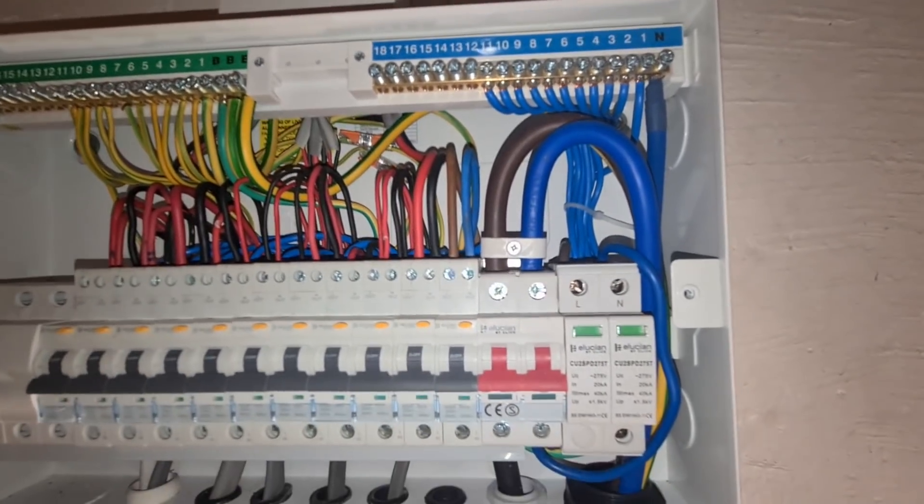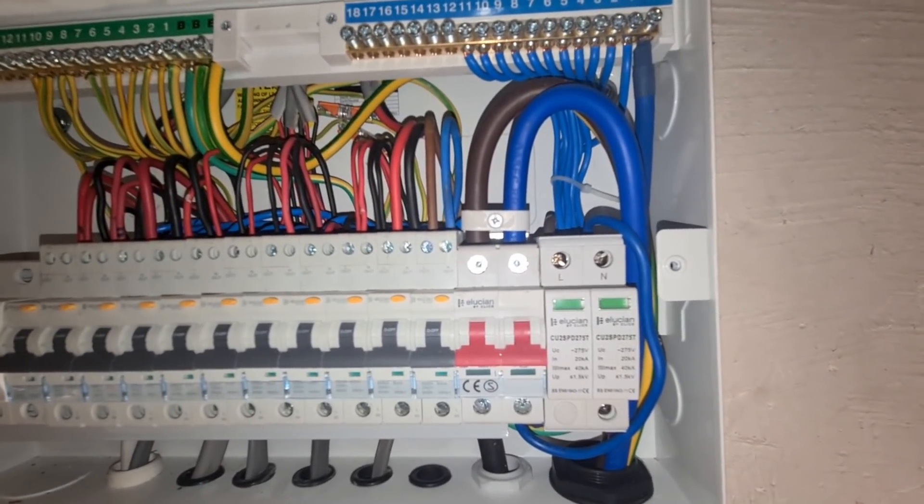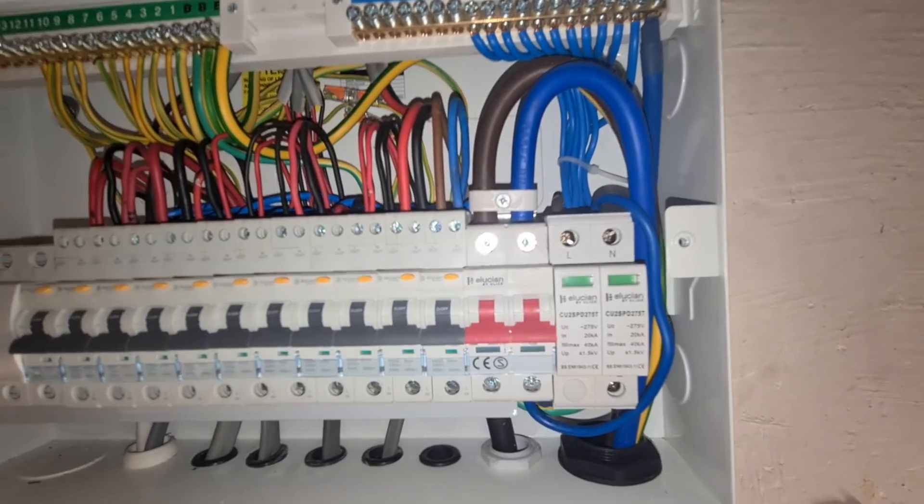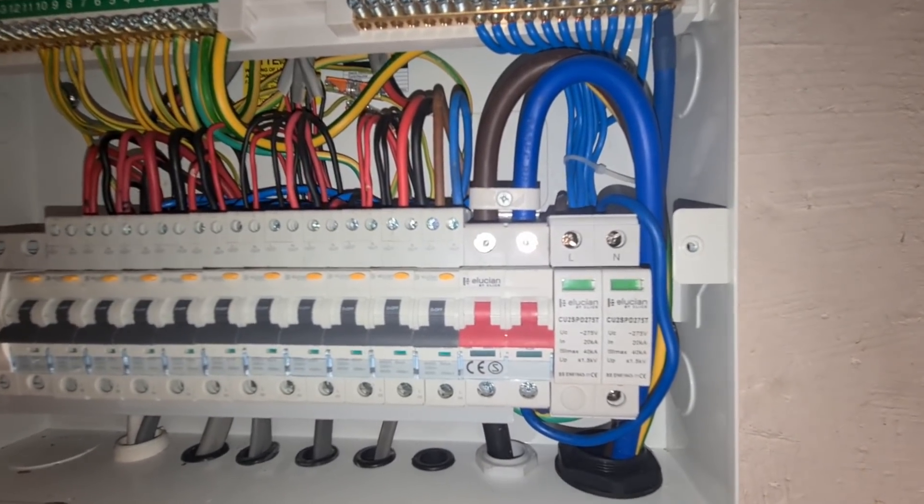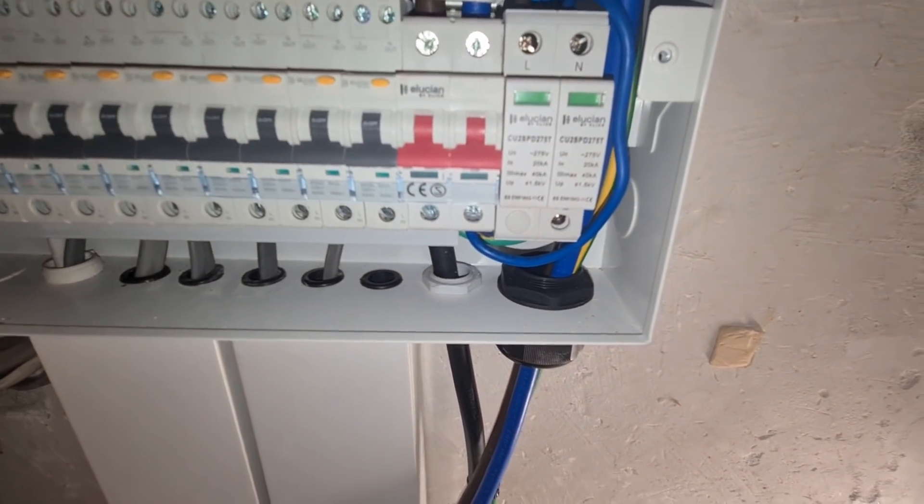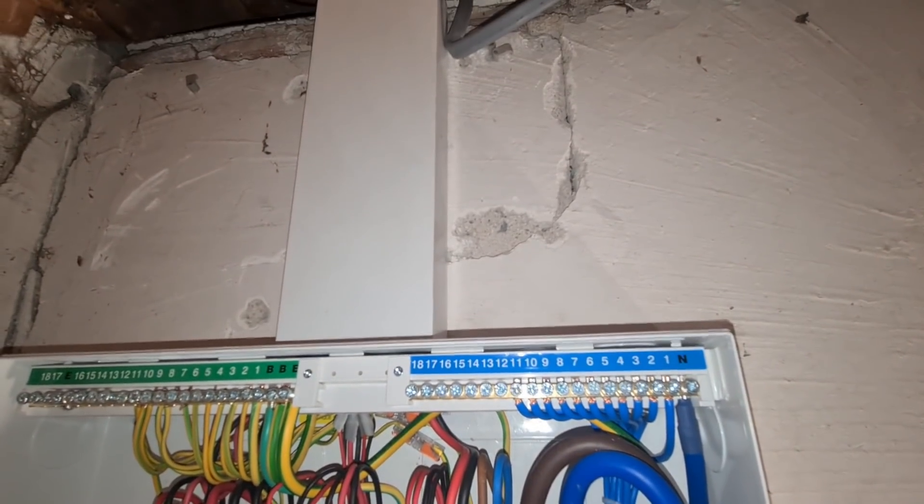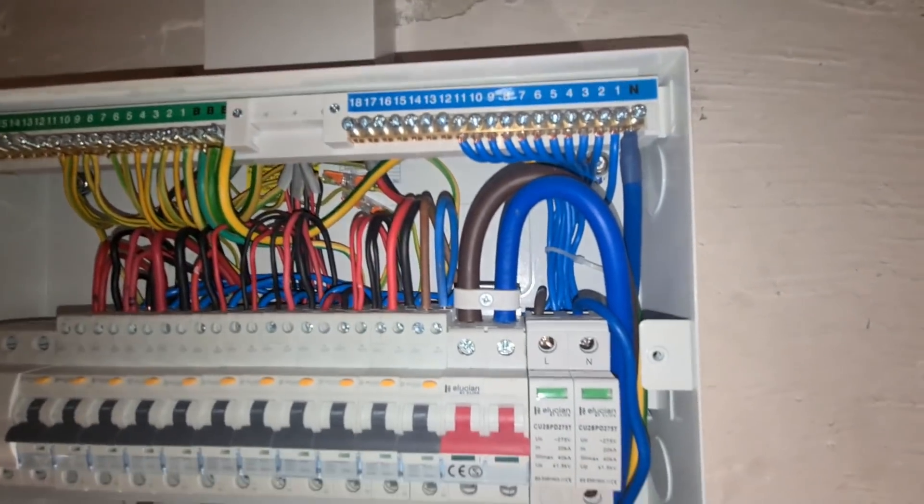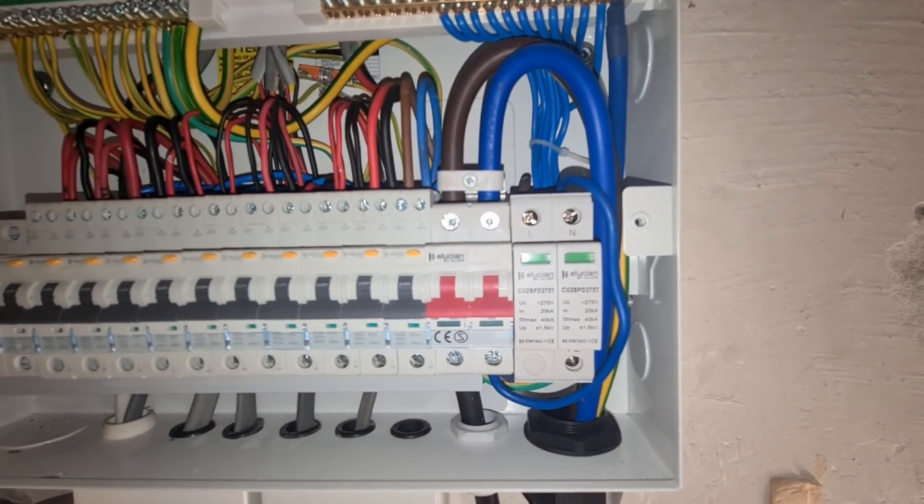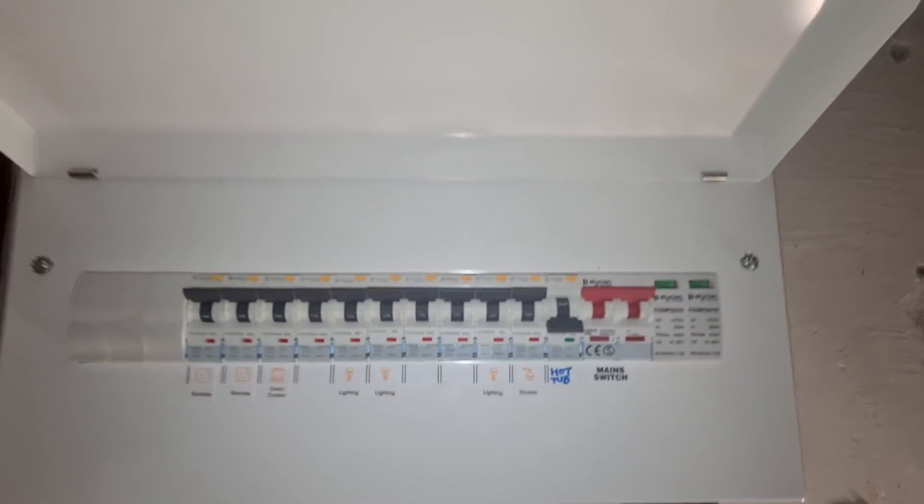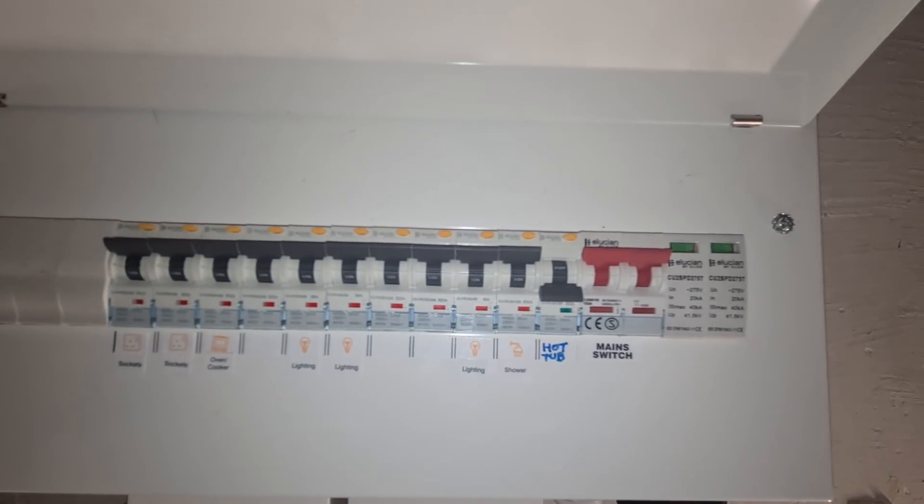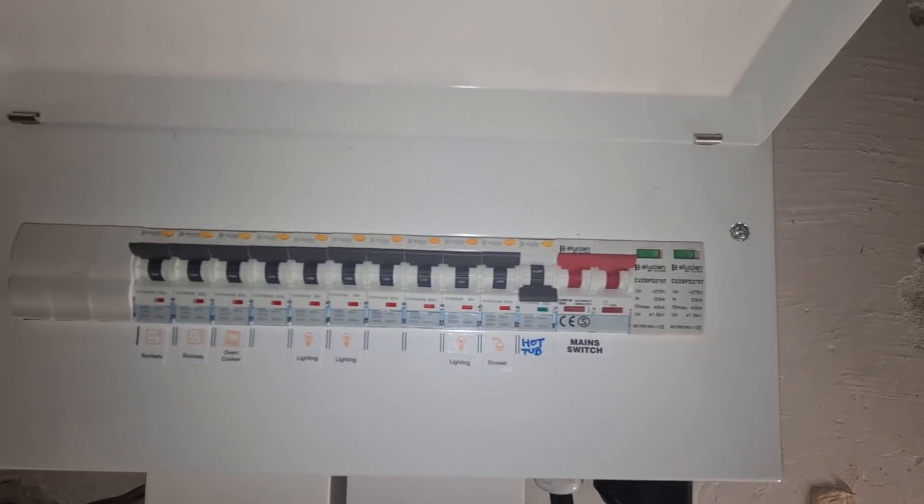So that's something I have to revisit. But there you can see the finished article so we've got the SPD in there at the end and that wires straight into the main switch, there's no overcurrent protection needed for that, and all the RCBOs. As you can see the grommets in the bottom there and also the grommets are in the top but you can't see them at the minute. There's the tail gland there, the trunking top and bottom. So that's neat, tidy outcome I think based on the length of cable I had. You can also spot those Wago connectors I was mentioning in the back of that board.